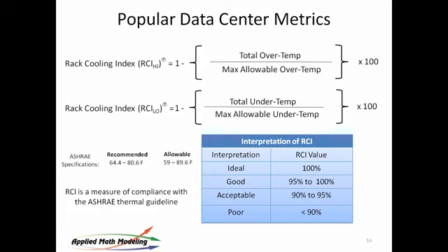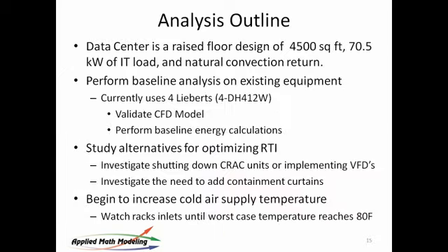Now, generally, the original idea was to use sensors to calculate these metrics. We use CFD to calculate these metrics, so we're actually getting it a little more detailed than could be done with sensors, because we have meshing, and meshing is a grid, and the grid is on the front face, and we can sample many, many points. But we've built these metrics into CoolSim 4, so you don't have to calculate these by hand anymore. In the DCEP training, they actually gave you spreadsheet methods for calculating these. You don't need to do that anymore when you use CoolSim. It's calculated as part of the overall process. So those are the three metrics that we're going to be using: PUE, RTI, and RCI.